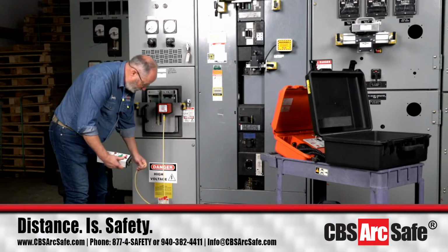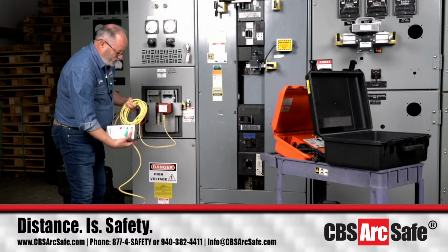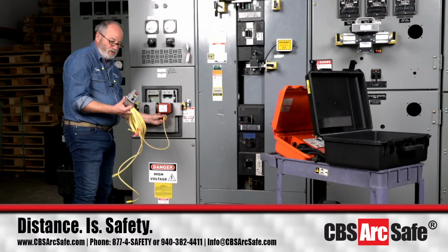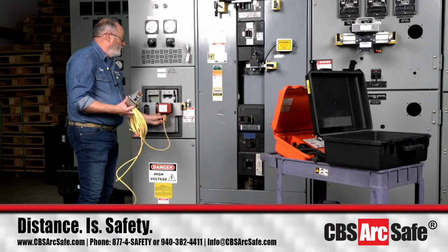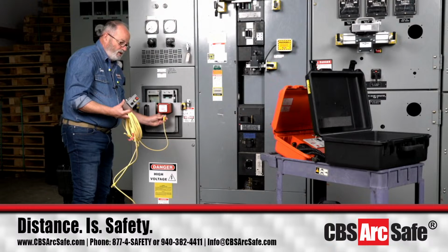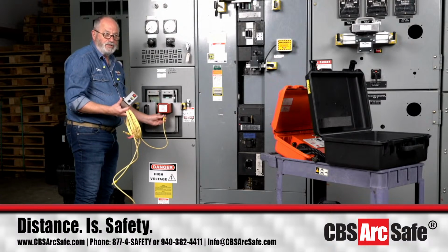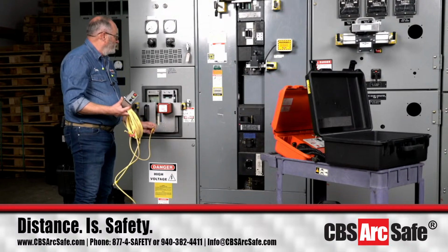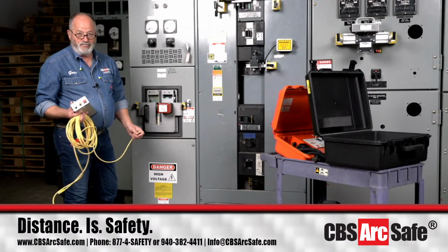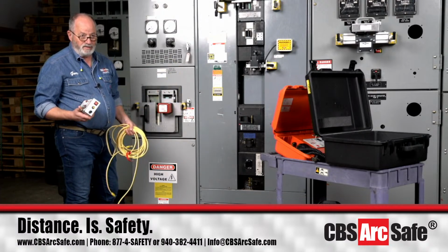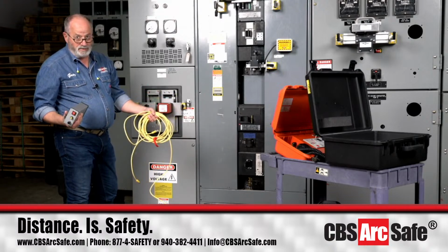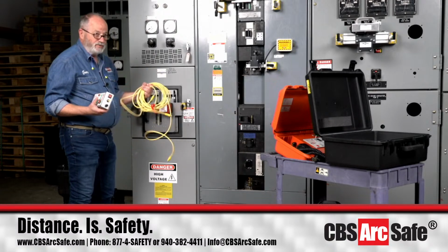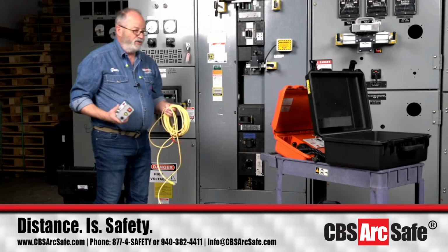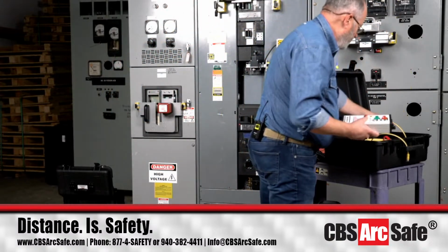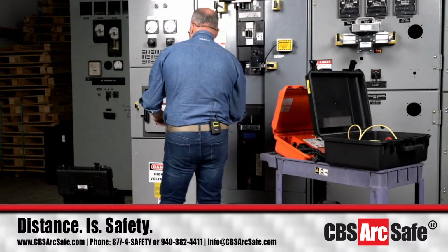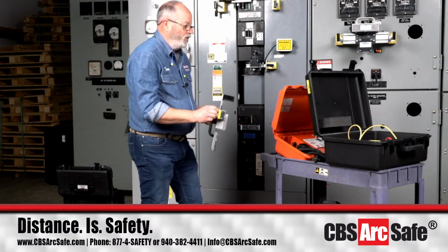Not all of our chicken switch series products are wireless yet, so some are still cable operated like this, whether it's a 30-foot or 50-foot cable. I've been in facilities where someone gets an arc flash study done and doesn't look at their own numbers. Their sticker says 60-foot arc flash hazard boundary, but they order an MDS30 when they actually need a 100-foot cable. We can do that, but we need to know what your sticker says for actual distance. That number means something, and you need the proper equipment to keep your employees outside the arc flash hazard boundary.